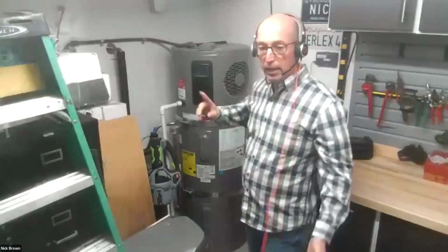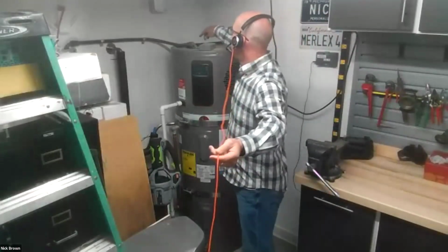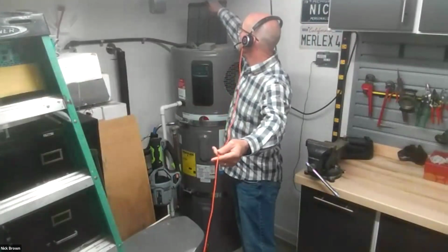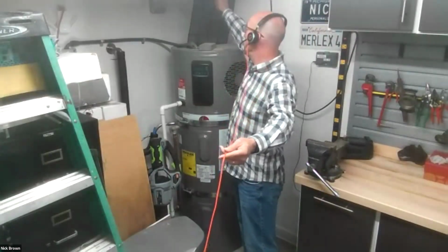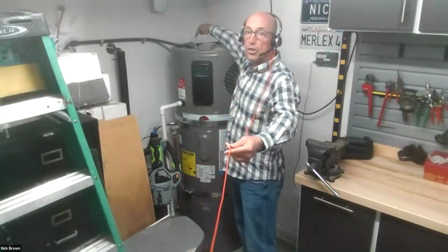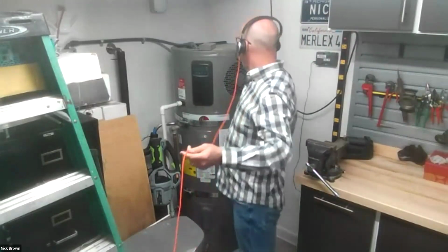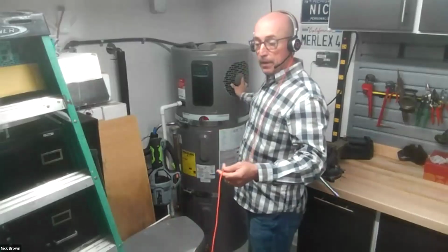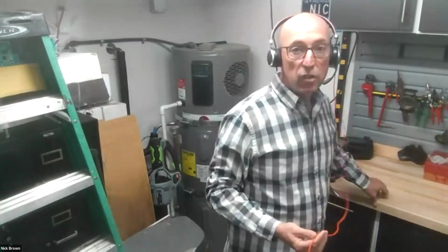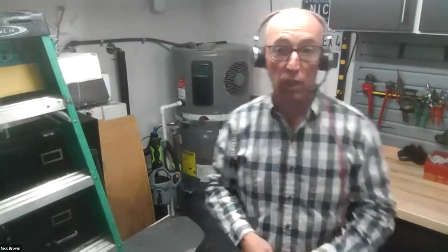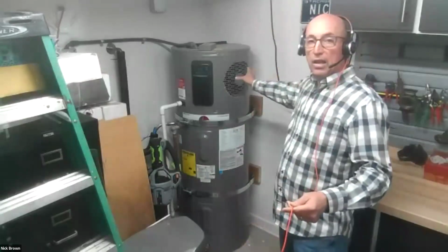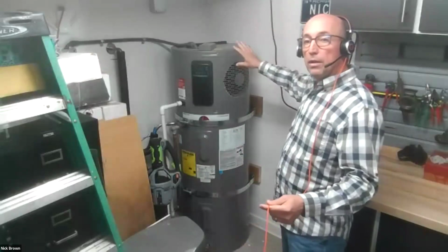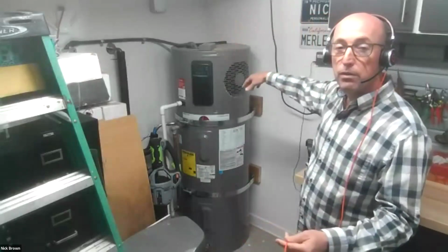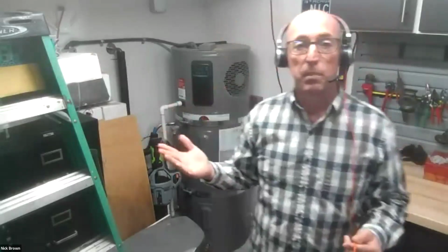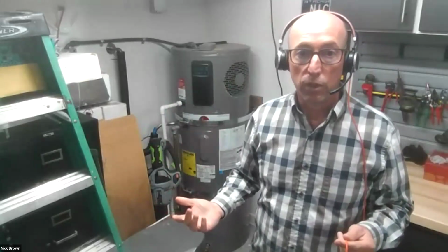First, I want you to see where the air goes on these. This is a Rheem 50 gallon unit, and it has an air filter up here. I just cleaned it so it's clean, but it pulls in hot air on the top through this grill and blows out cold air right here on the side. So in my case, my workbench gets cold air blown on it when the heat pump water heater runs. Notice we oriented this outlet so it wasn't up against a wall, so it could get nice free airflow. A garage is a big enough space where there should be plenty of warm air around it for the heat pump water heater to do its job.